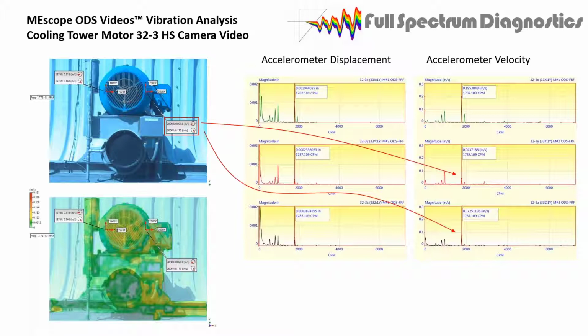In fact, I don't have it with me, but I had a motor pedestal that was cracked, and I just took a quick video and you could see the crack opening up. You couldn't feel it. You couldn't feel any pinch, but with the software enhancement, you could see the crack moving. So we could tell it was still propagating.